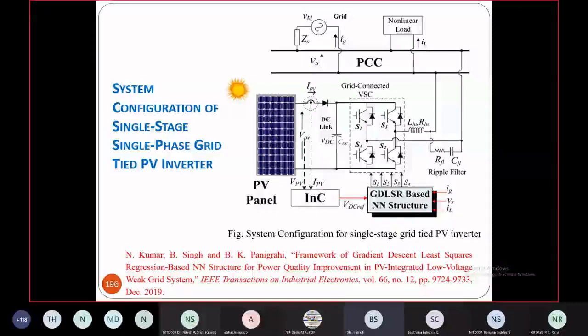Normally it depends - that's why the manufacturer isn't ready to install in some places since they're supplying single stage systems. So you have applications where you might not have partial shading except from clouds. And the voltage even in that single stage varies from 560 volts to 850 volts in a 3-phase system.